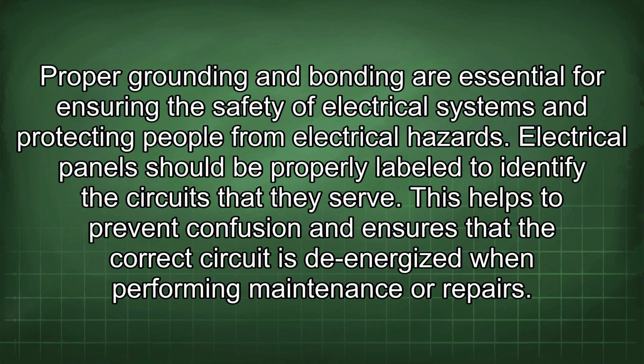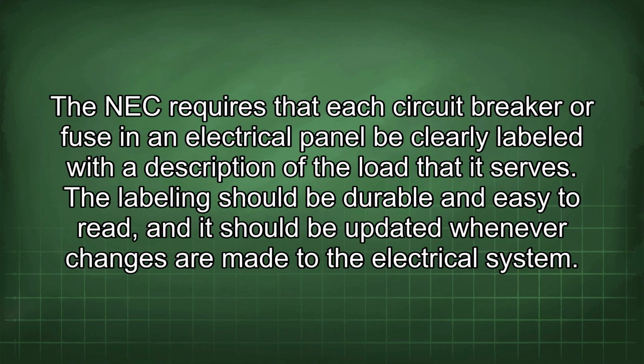Electrical panels should be properly labeled to identify the circuits that they serve. This helps prevent confusion and ensures that the correct circuit is de-energized when performing maintenance or repairs. The NEC requires that each circuit breaker or fuse in an electrical panel be clearly labeled with a description of the load that it serves.